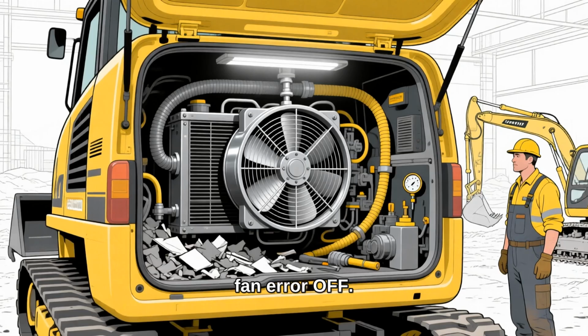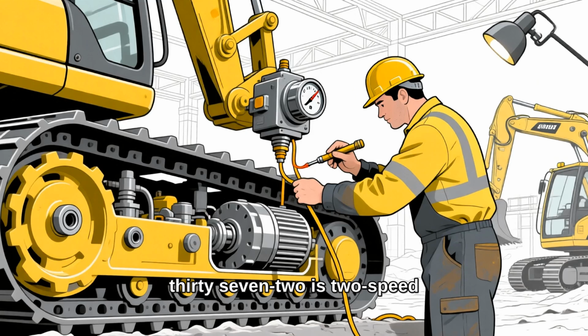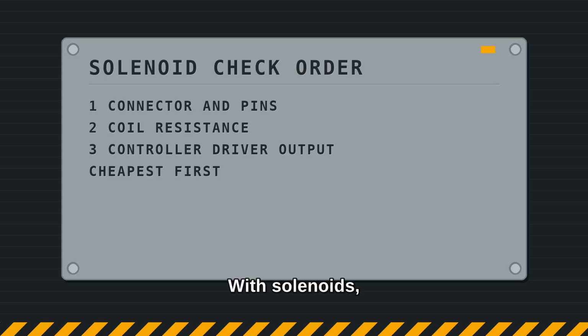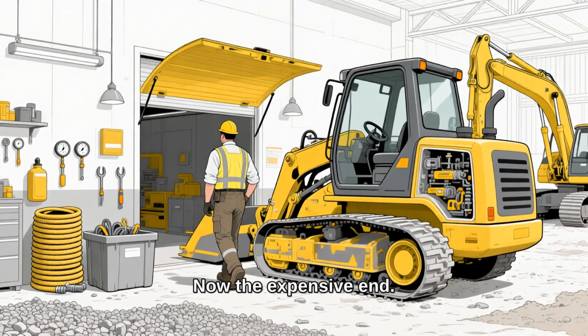35.3 is hydraulic fan error off. Cooling, that one command is how a normal day turns expensive. 37.2 is two-speed secondary error ON, the circuit behind your travel speed change, not the drive itself. With solenoids work the cheap end first, connector, then coil, then the driver inside the controller. Now the expensive end. And here's the strange part. The codes get vaguer as the parts get pricier.